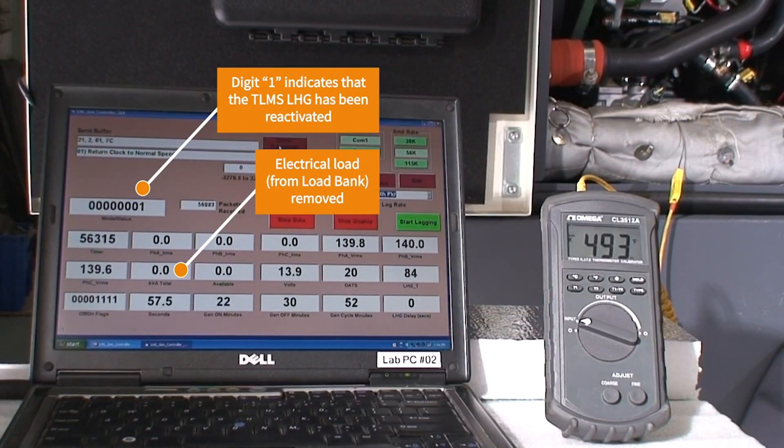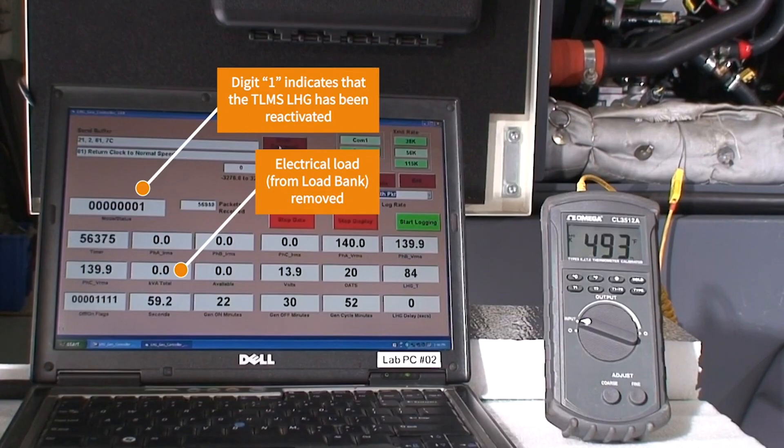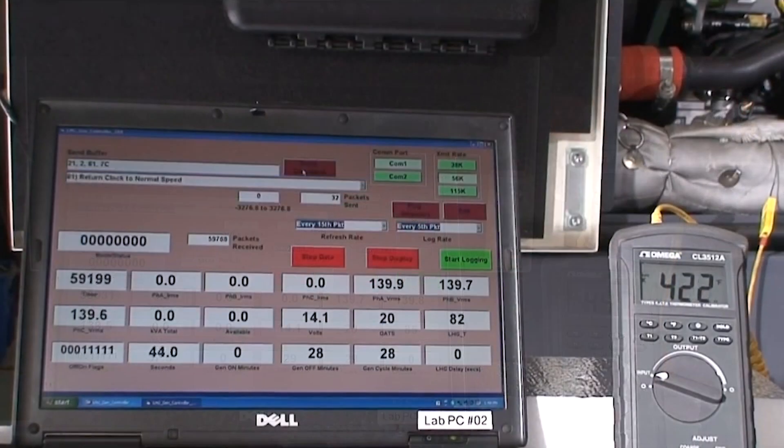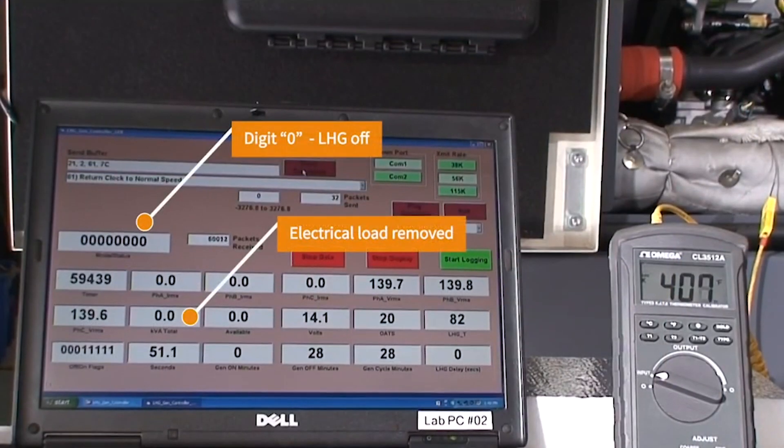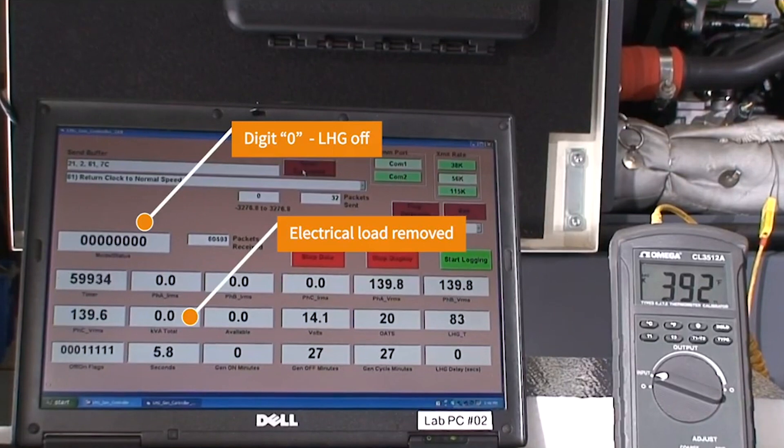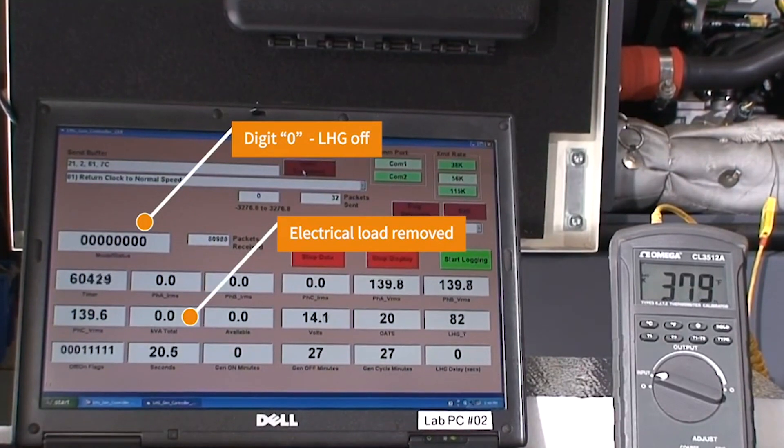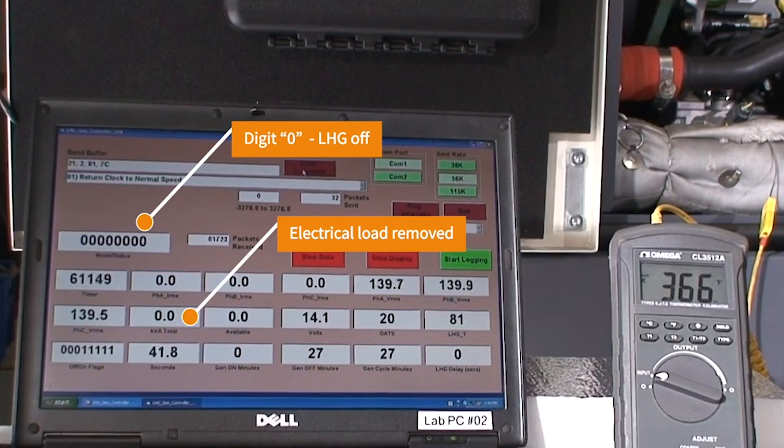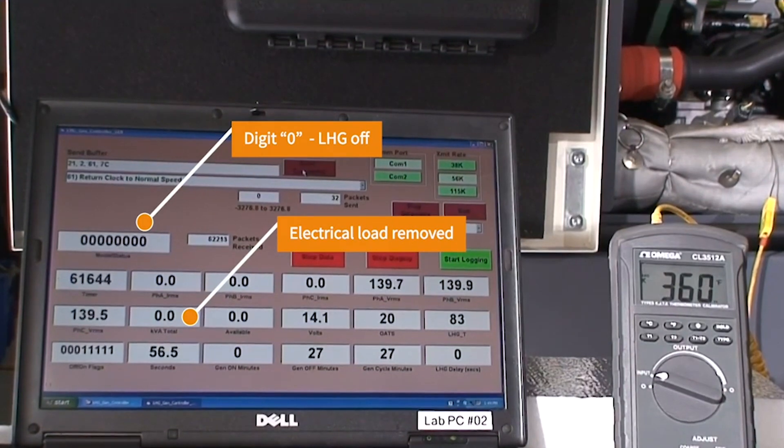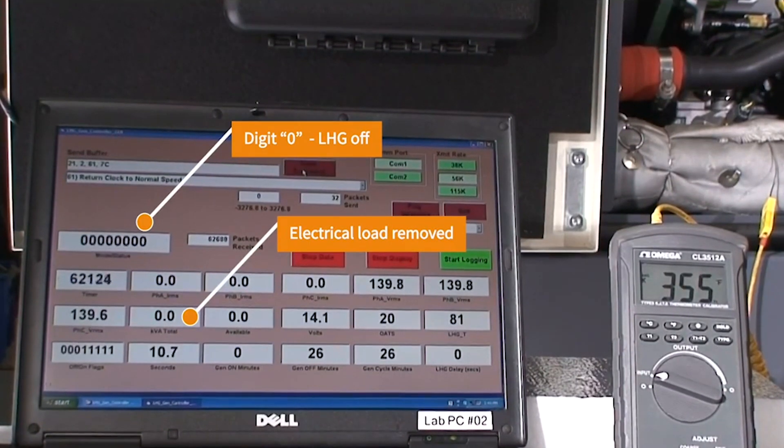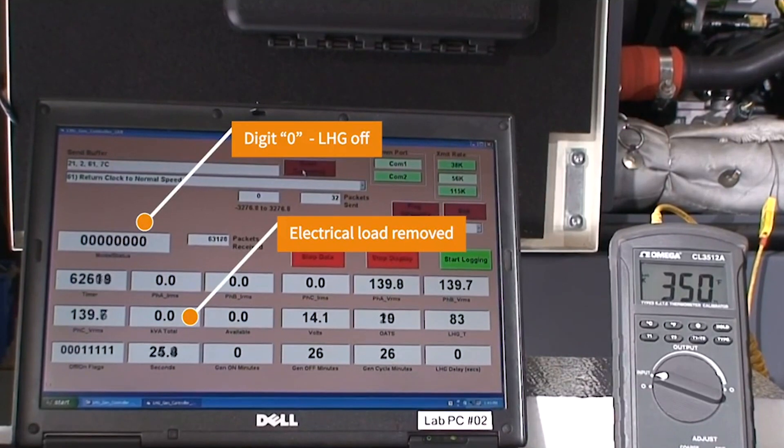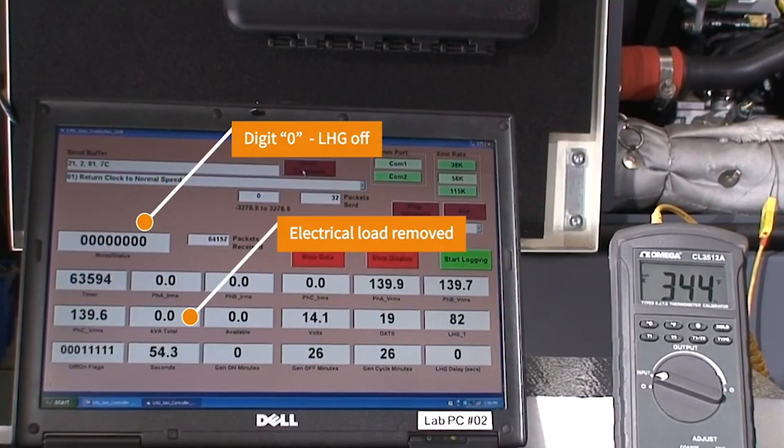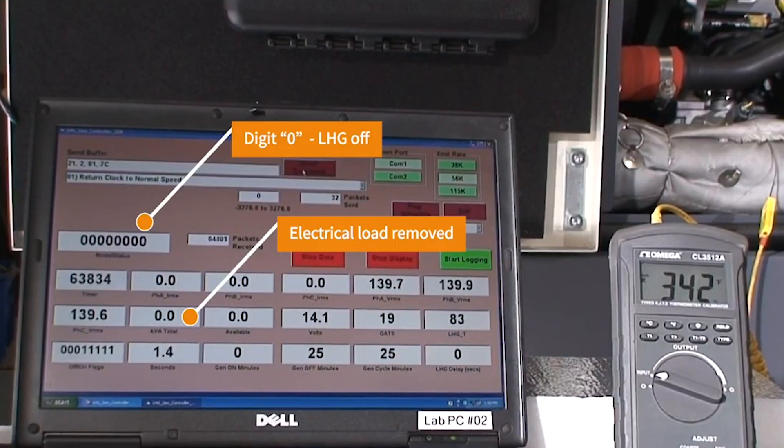If we now deactivate the LHG and we leave the load bank turned off, the engine is now unloaded and the exhaust gas temperature rapidly reduces back down to about 338 degrees Fahrenheit. This is indicative of what happens when a diesel generator is operated unloaded. Please note that this portion of the video has been sped up to minimize the viewing time.